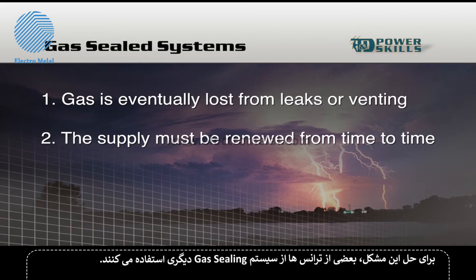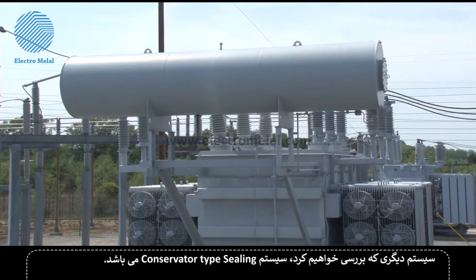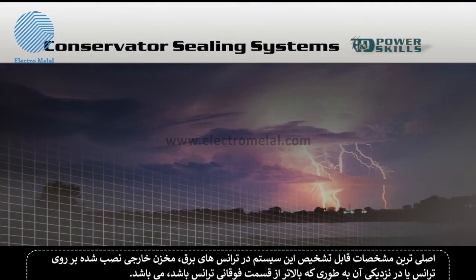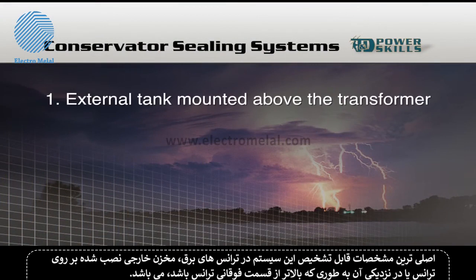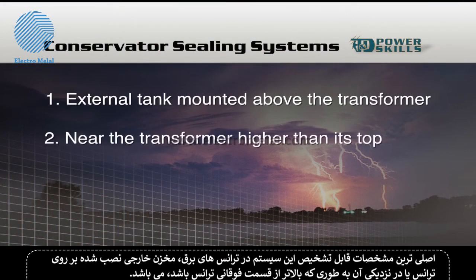To avoid this problem, some transformers use other sealing systems. The next system we're going to look at is a conservator-type sealing system. The main recognizable feature of conservator-type sealed power transformers is an external tank mounted above or near the transformer at a level that is higher than the top of the transformer. Let's look at an example.